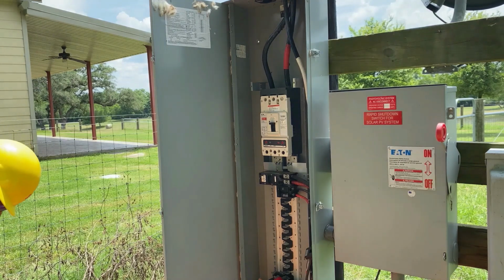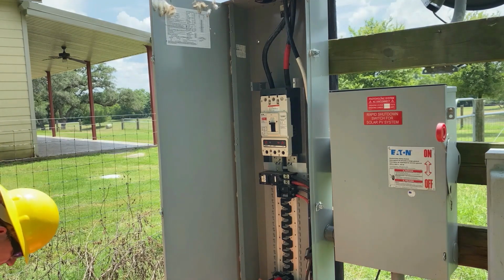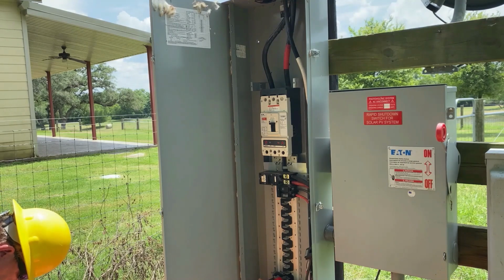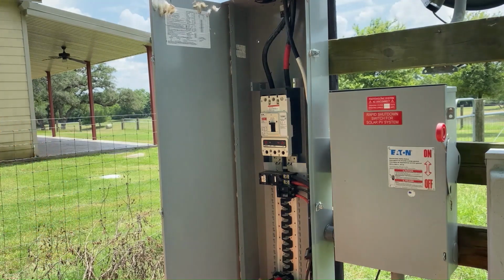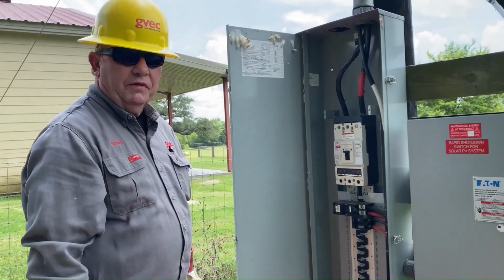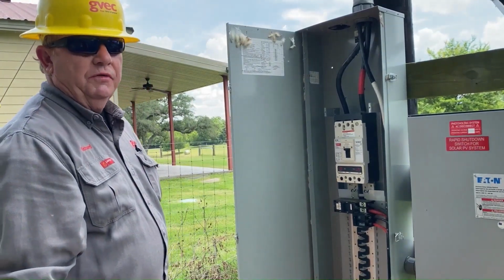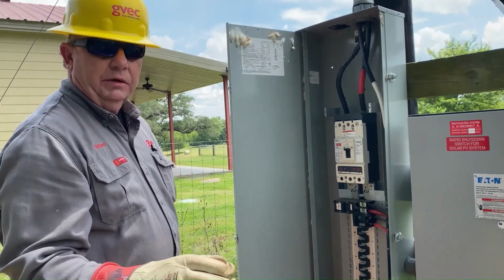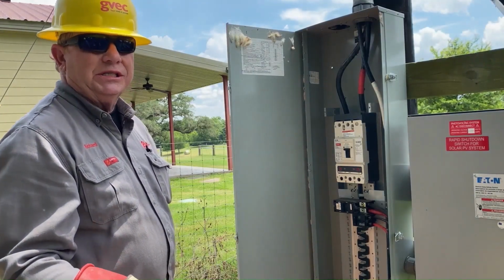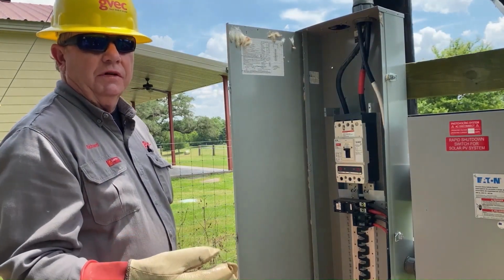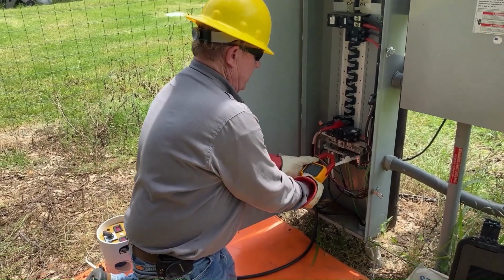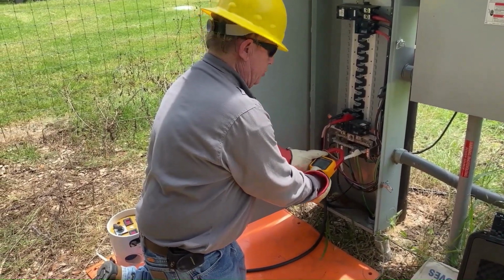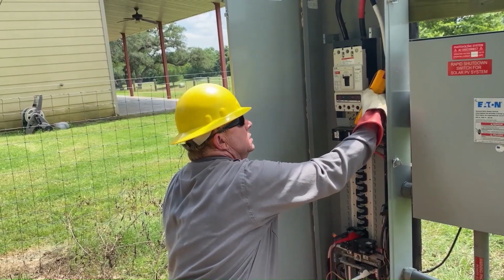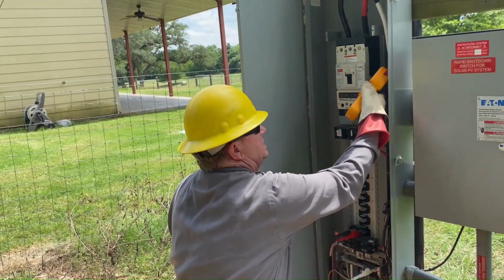Now I'm going to move that load to the right hand side. Our voltages start out 125 and 120. I'm going to make it worse. 130, 115. So now that we've got the Super Beast running at 120 volts, we're going to unpack the flicker buster, which is a 26 amp load, and we're going to move it to the other side. Right now the Super Beast is dumping 22 amps on that neutral. 21.6.